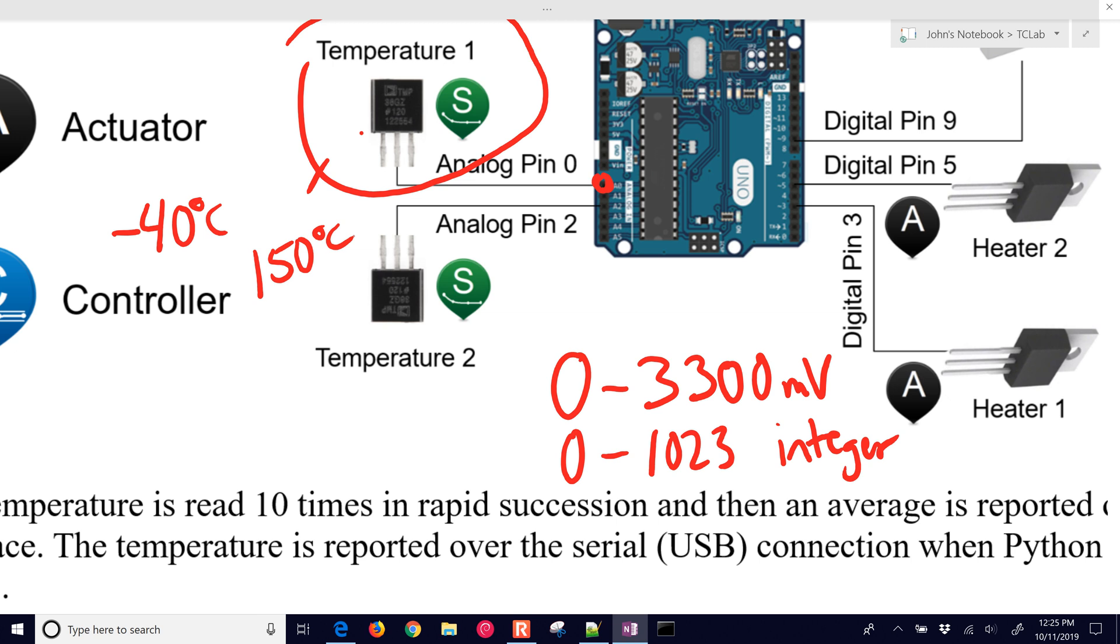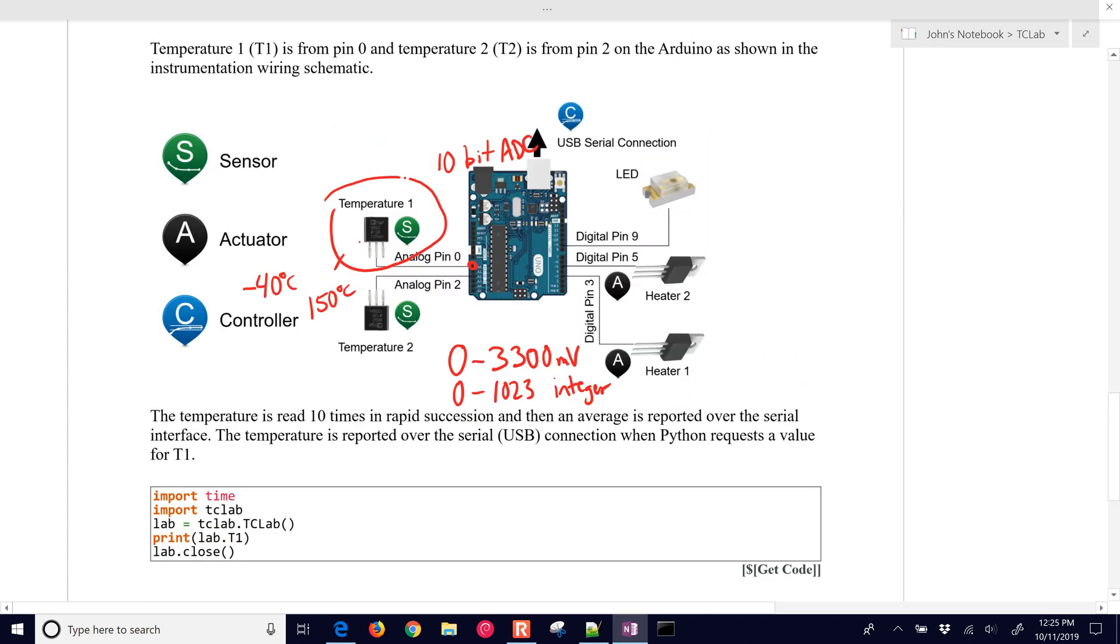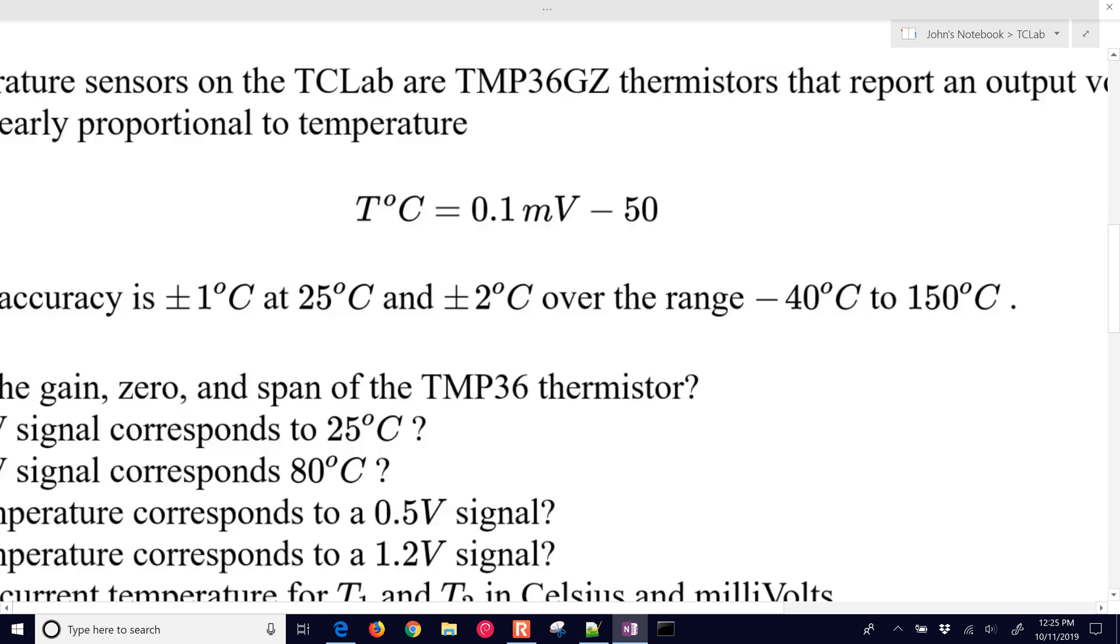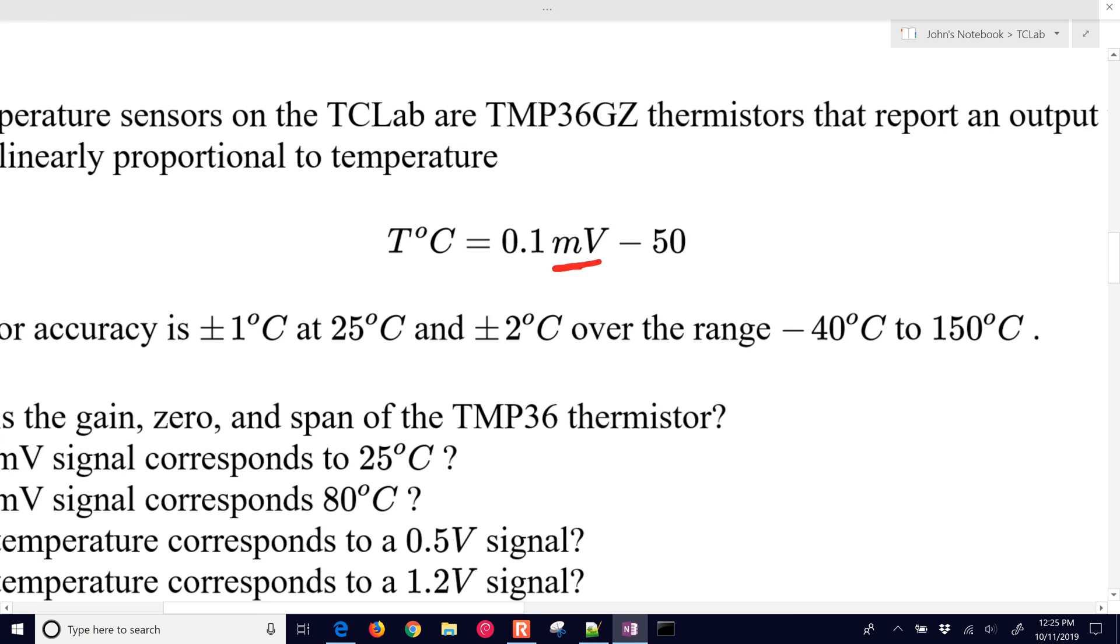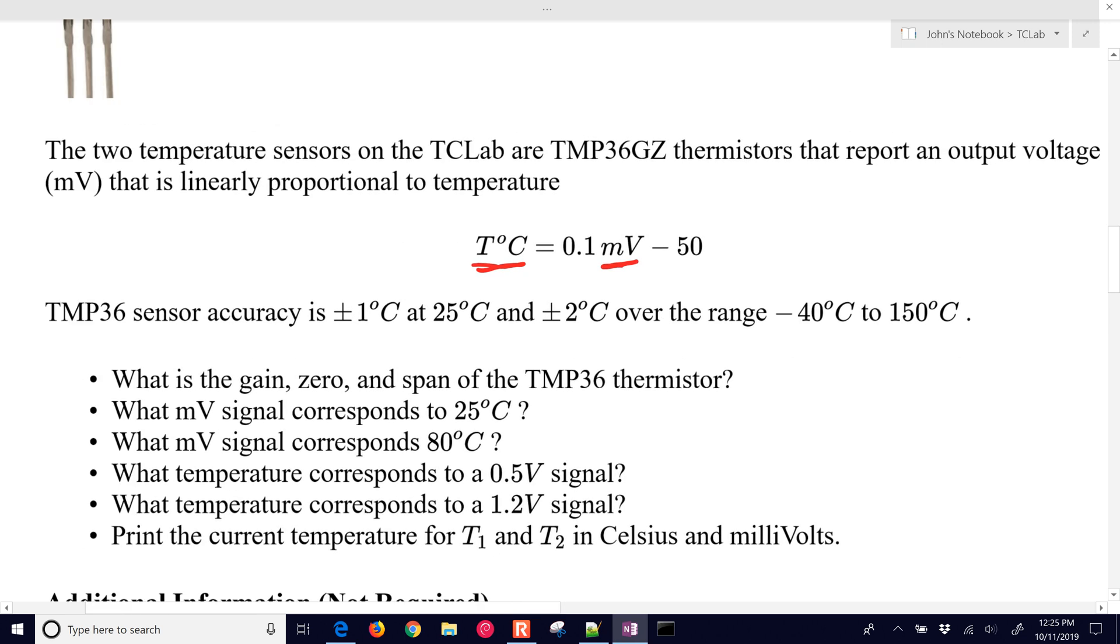We're going to determine, with this exercise, what is the gain, zero, and span of this. Once it's converted to the integer, we then use a formula to convert it to degrees Celsius. Here is the formula that we use, millivolts into degrees Celsius, and information about the accuracy. It's plus or minus 1 degree Celsius at 25 degrees Celsius, and plus or minus 2 degrees Celsius over the entire range. These sensors don't need calibration. They are thermistors that have a temperature effect, and they return a different millivolt based on the temperature.